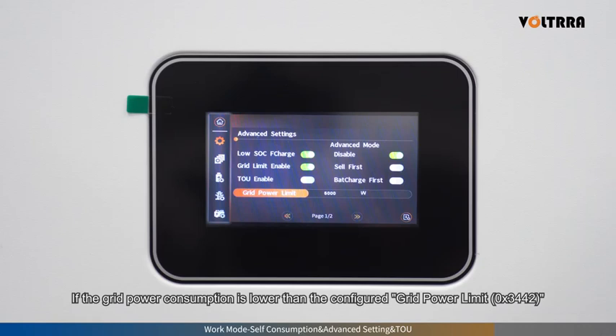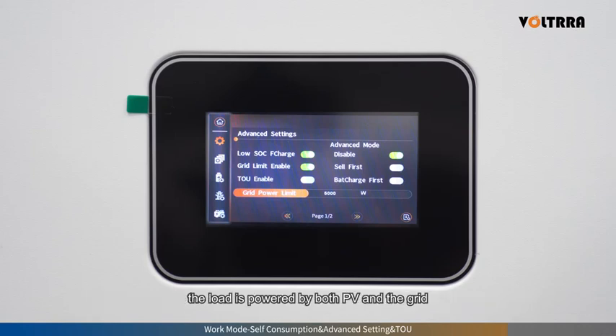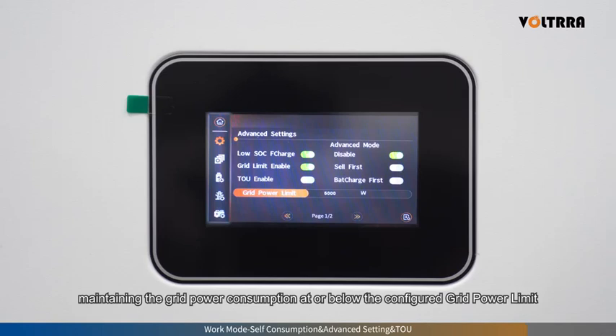If the grid power consumption is lower than the configured grid power limit, the load is powered by both PV and the grid, and the battery does not discharge. When the grid power consumption exceeds the grid power limit, the battery starts discharging to supply the load, maintaining the grid power consumption at or below the configured grid power limit.